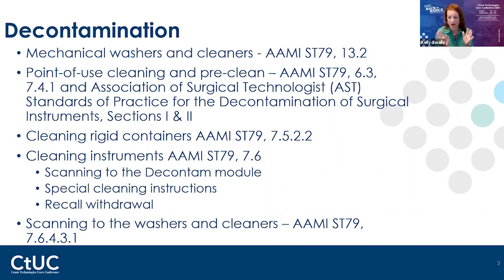I don't look at the tape. I don't look at anything. Little did I know that you pushed basin for your cycle, and it's a whole load of instruments. So those instruments never got their instrument lubrication, and it was a short, quick cycle because basins are pretty much nothing, no cracks or crevices in those instruments to get clean. So if you run that basin, did those instruments really get cleaned?